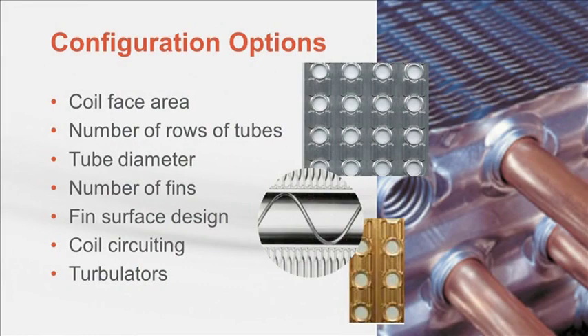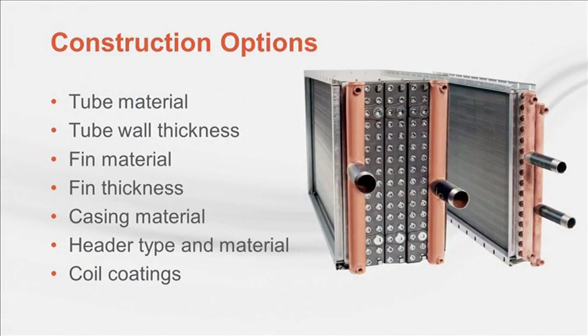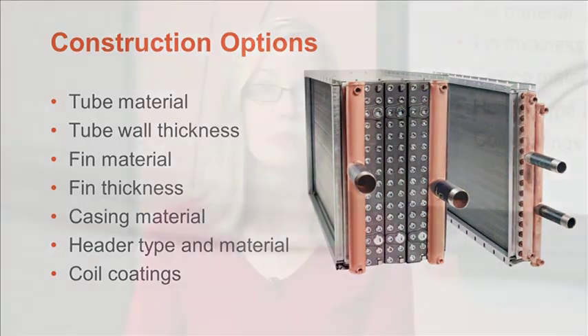The primary characteristics of HVAC water coils include the face area of the coil, the number of rows and diameter of the tubes, the number of fins and the design of the fin surfaces, the length of each circuit and the number of tubes fed, and whether or not the tubes contain turbulators. Construction options also include materials and thickness of tubes, fins, and casing, the types of headers used, and coil surface coatings. All of these options help project teams select the optimal coil design for a given project.